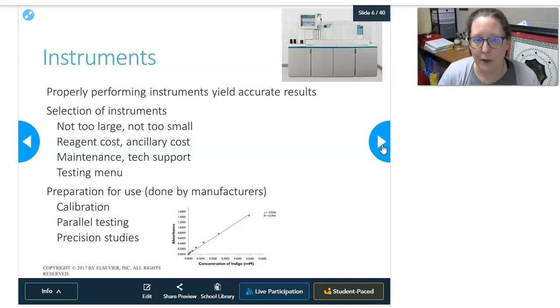Okay. Preparing the instrument for use is also part of quality. This is often done by the manufacturers. So let's say you buy a new analyzer, or you're replacing your old analyzer with a new one. The company that you're buying the analyzer from will send one of their techs, and they will help get the machine up and going and do all the work that it takes to get it running. So there are things like, for example, once that machine is installed, every single test that it runs will have to be calibrated because it's the first time it's running all of this.